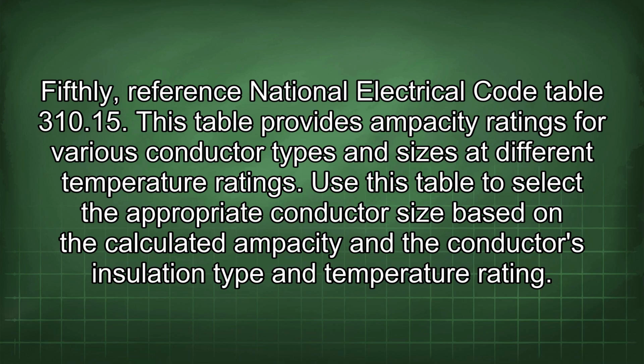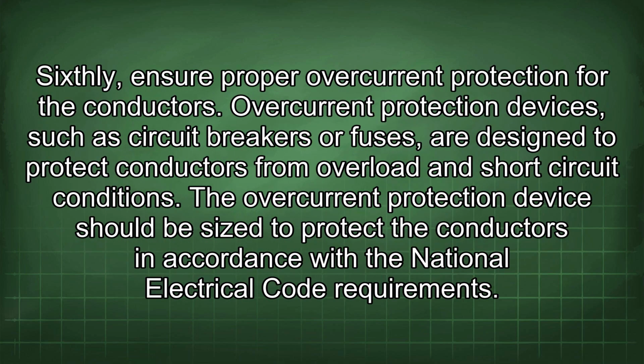This table provides ampacity ratings for various conductor types and sizes at different temperature ratings. Use this table to select the appropriate conductor size based on the calculated ampacity and the conductor's insulation type and temperature rating. Sixthly, ensure proper overcurrent protection for the conductors. Overcurrent protection devices, such as circuit breakers or fuses, are designed to protect conductors from overload and short-circuit conditions. The overcurrent protection device should be sized to protect the conductors in accordance with the National Electrical Code requirements.